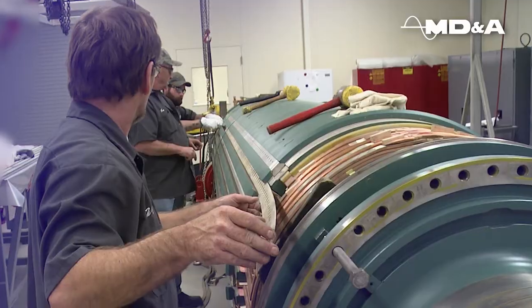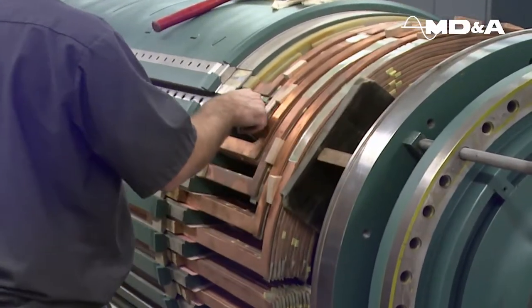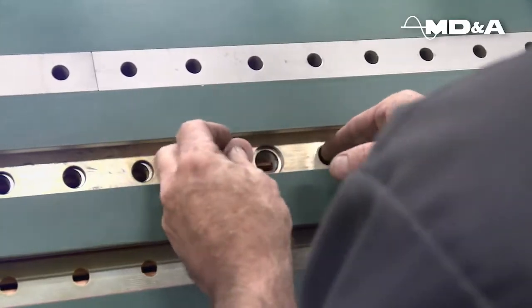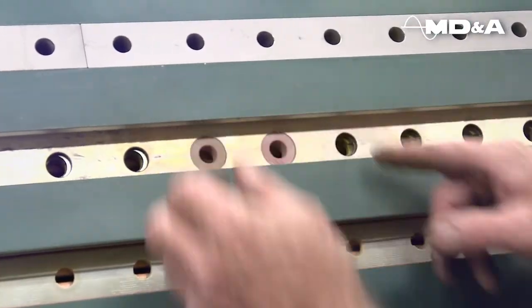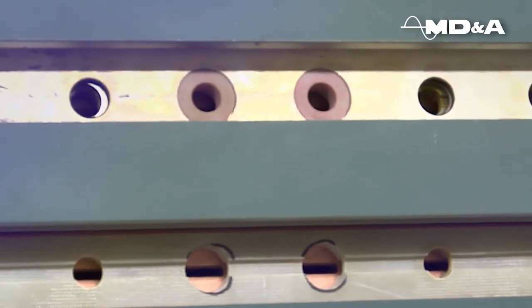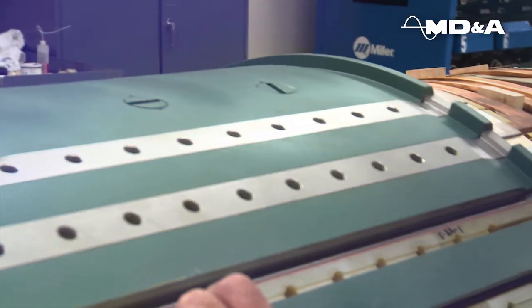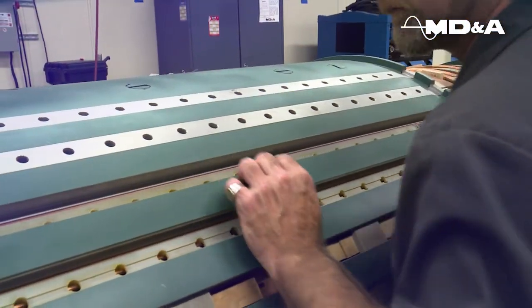As MD&A experts complete the full assembly of creepage, top hat, spring with filler, amortiser, and wedges, we verify that all the slot components and vent holes are lined up correctly so there is no blockage. From start to finish, we ensure the precision, quality, and integrity of your spring migration repair.